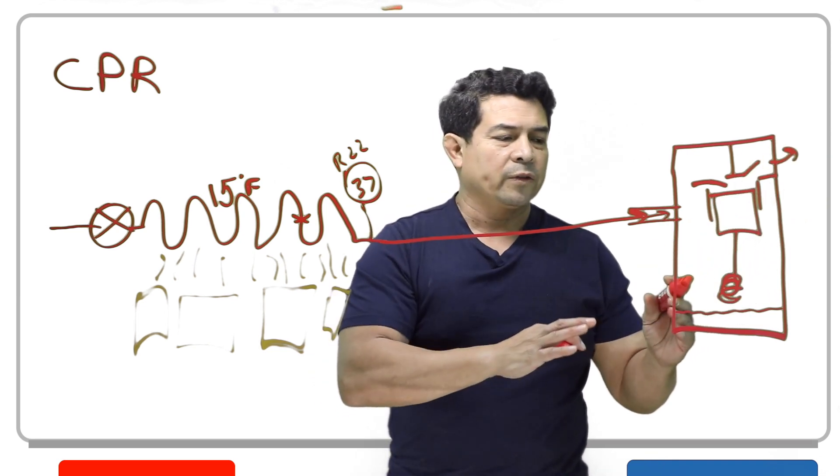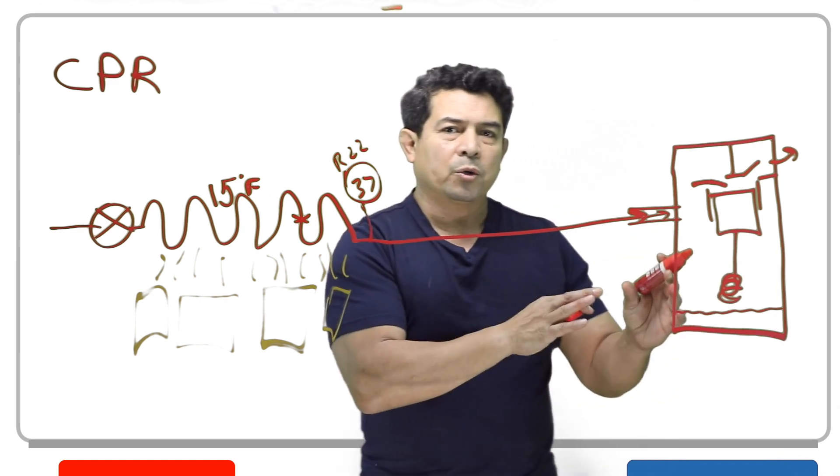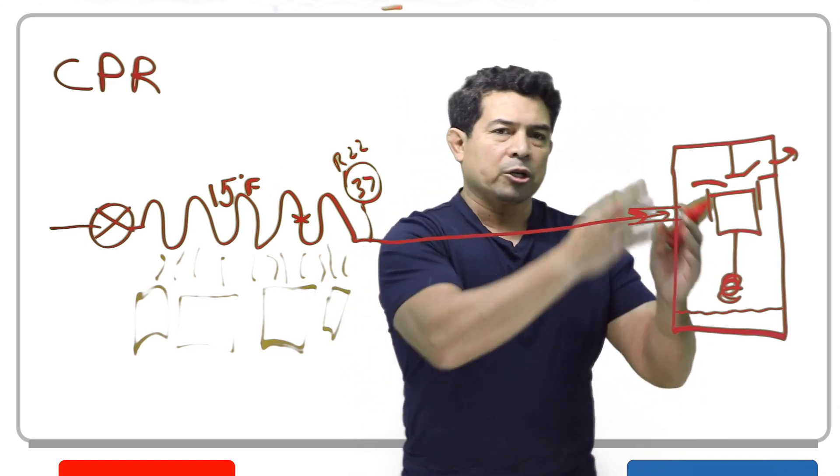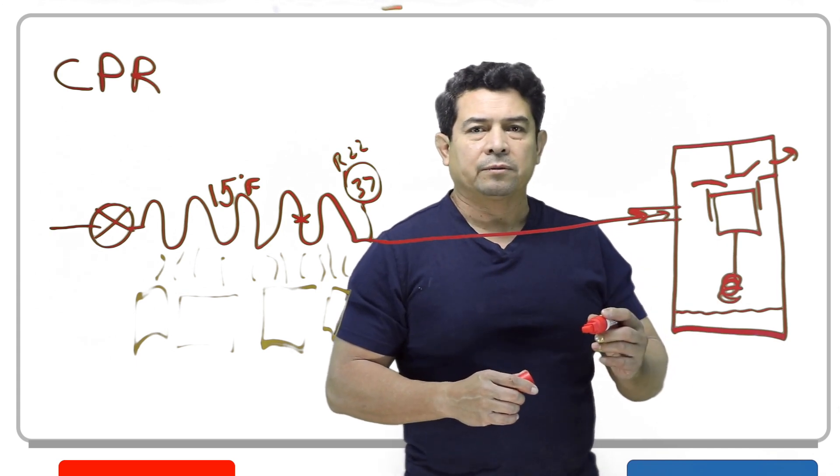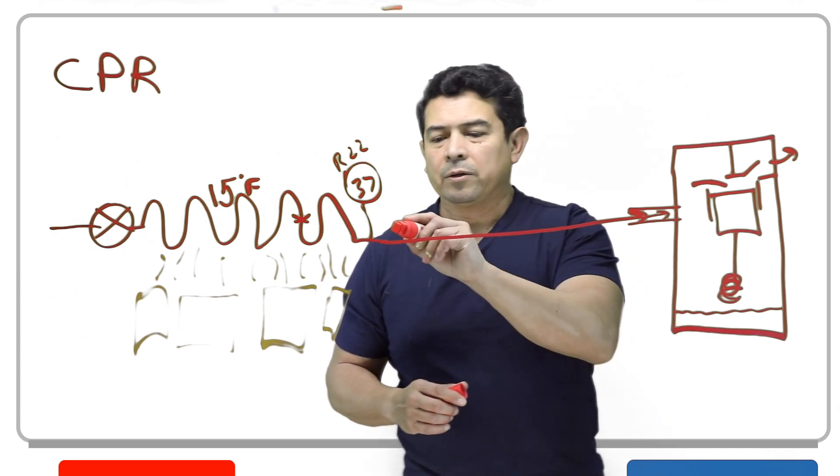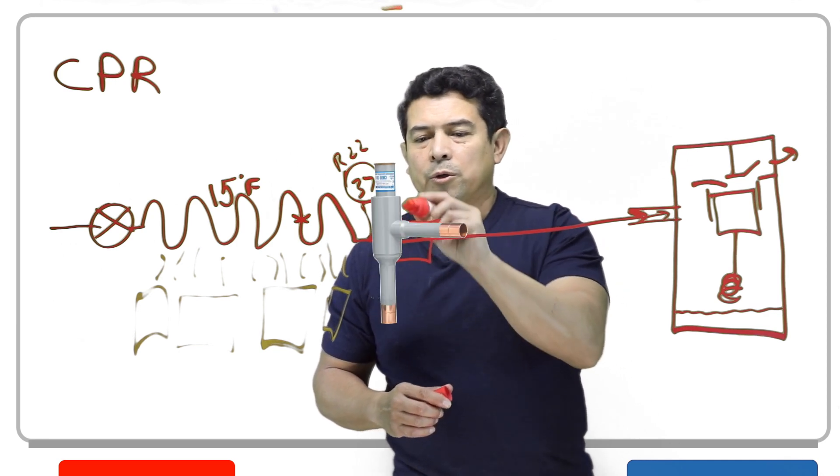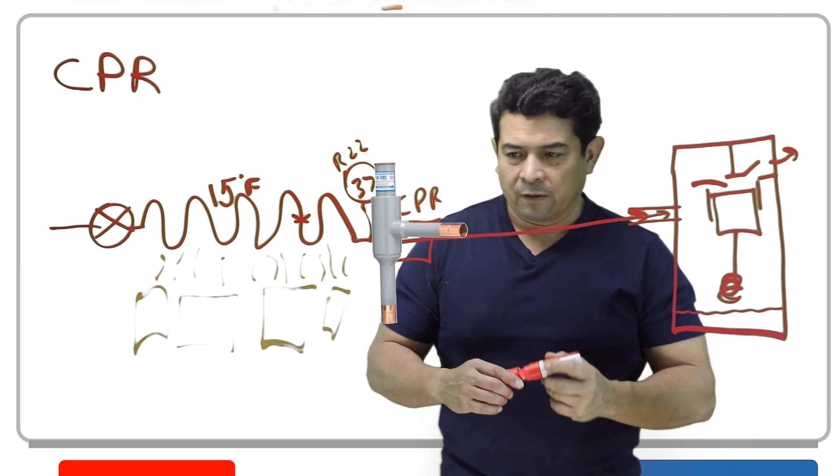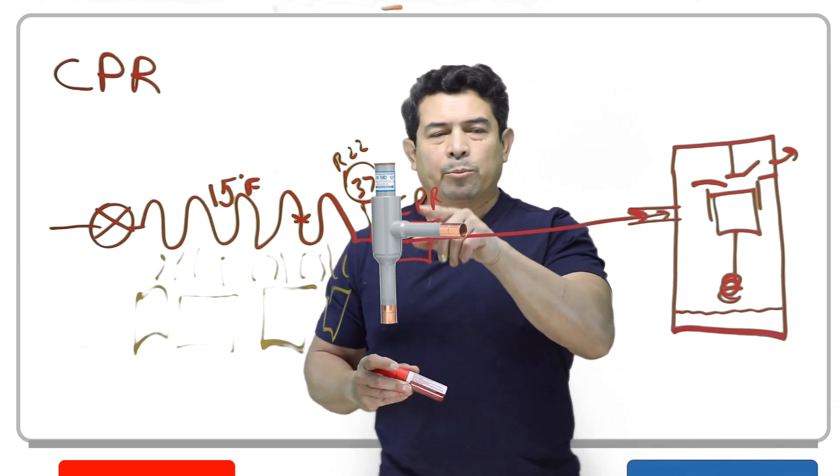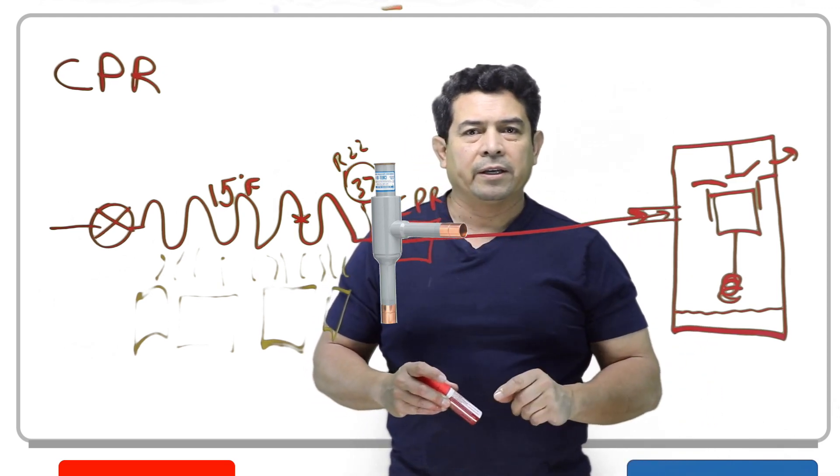If we overwork this compressor, if the suction pressure goes up too high, our pressures are going to climb. And when that happens, the compressor is going to overload. To keep that from happening, then we place your CPR valve right there. This is going to regulate the pressure that's going to the crankcase.